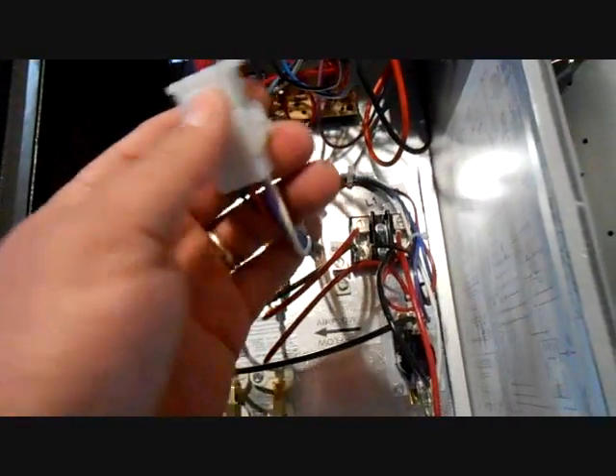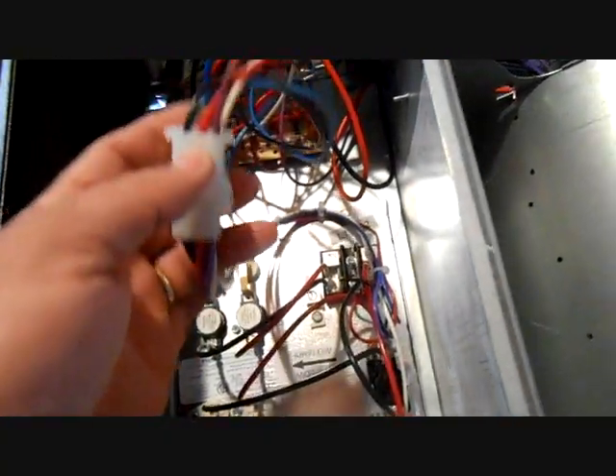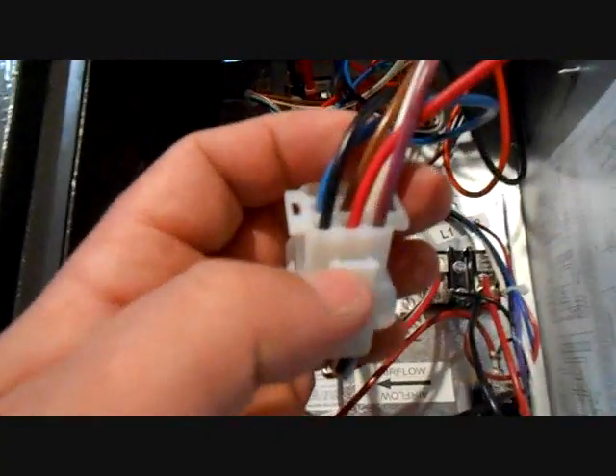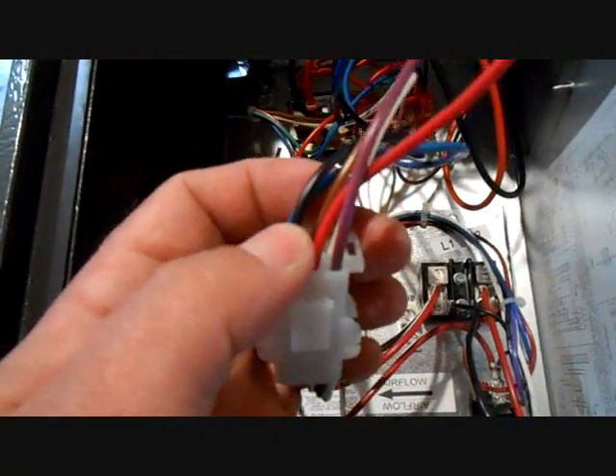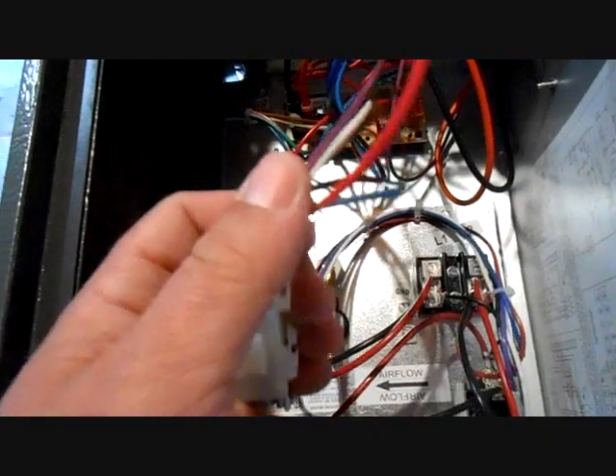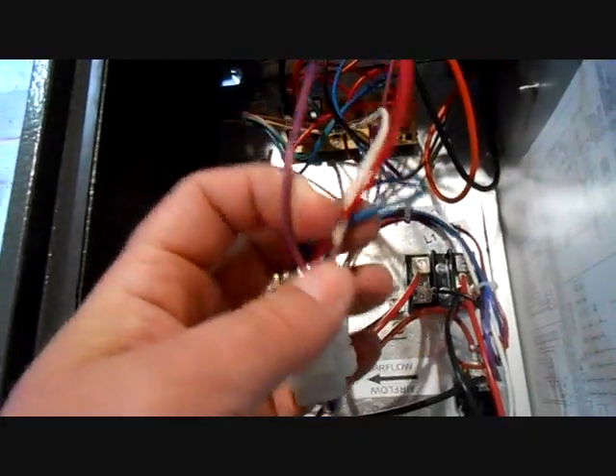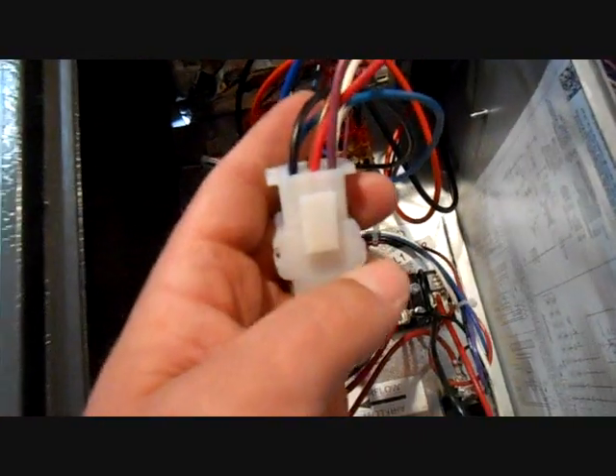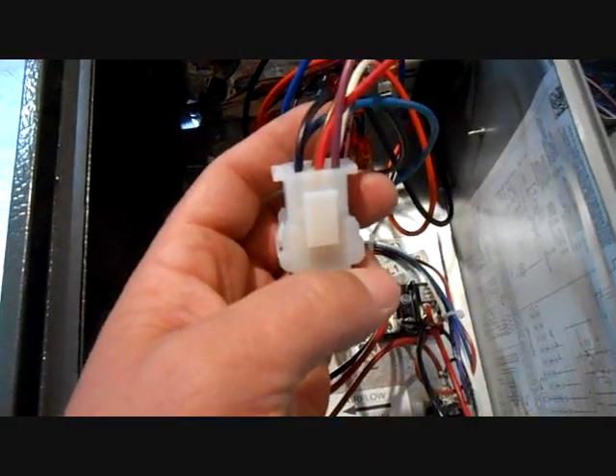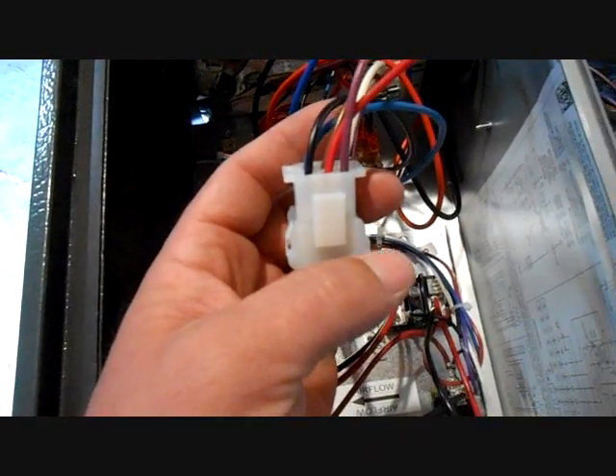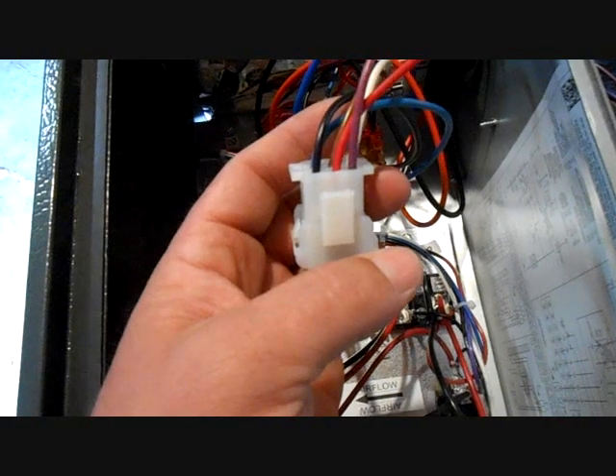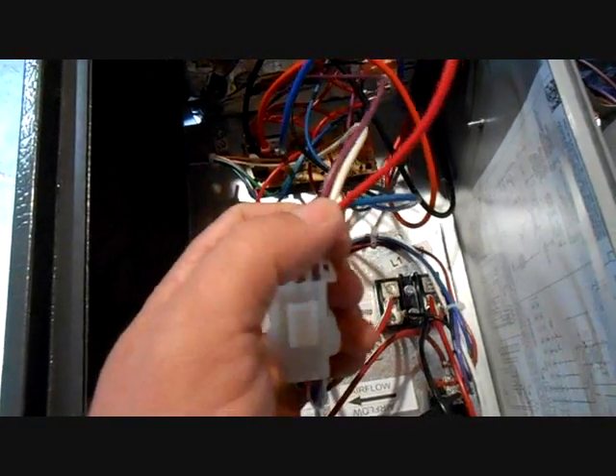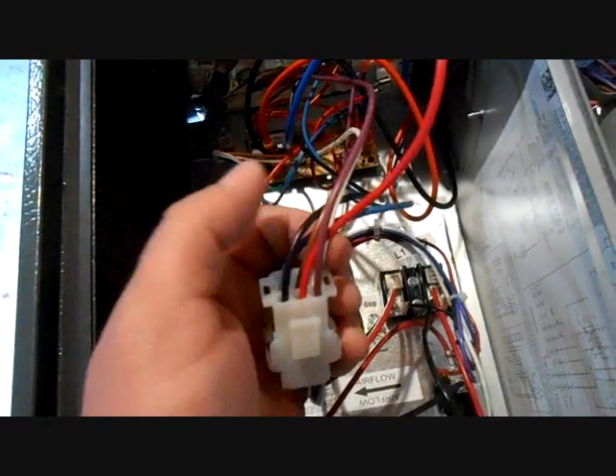Here's our plug. Wire is coming out of the heater to the rest of the unit. We have our L1 and L2 black and red. We have a purple high voltage wire going to the blower relay. That is coming from the heat strips. As you see down here on top of the sequencer you have our purple wire that is going in to power the blower. In the case of there's no blower call from G. 24 volts. The heat strips are on. This will power the blower.